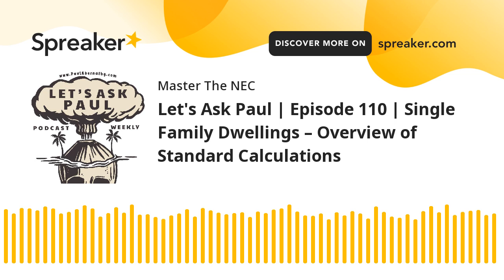And if you're in the 2020 code, what I want you to do is go to 220.14(J). Okay, that's where I want you to be. All right, once you're at 220.14(J), let's read it real quick. It says dwelling units. Well, that's what we're doing, right? One family dwelling. It's a dwelling unit.